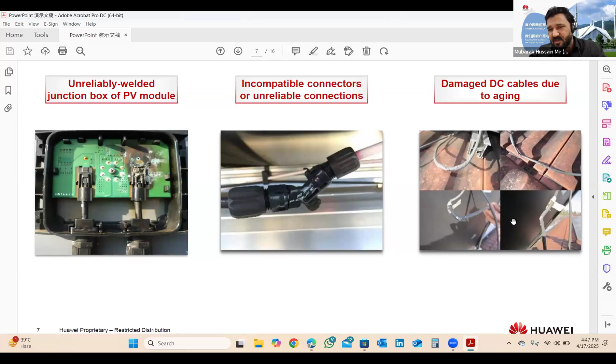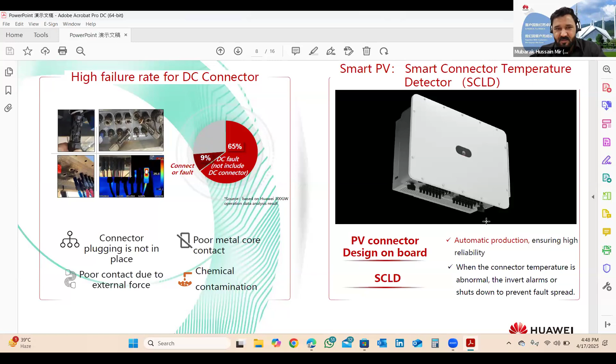This is the one smart connector level disconnect. Actually, we can already see it in the presentation: because of human error, anything could happen, like an MC4 connector damage or a spark. So in the Huawei inverter, there's a smart connector temperature detector sensor available at every MPPT. At every connector, there is a smart sensor available. It detects the spark and the temperature. At a certain temperature level, it automatically disconnects the whole inverter. So this is the biggest saver of inverters and the plant.